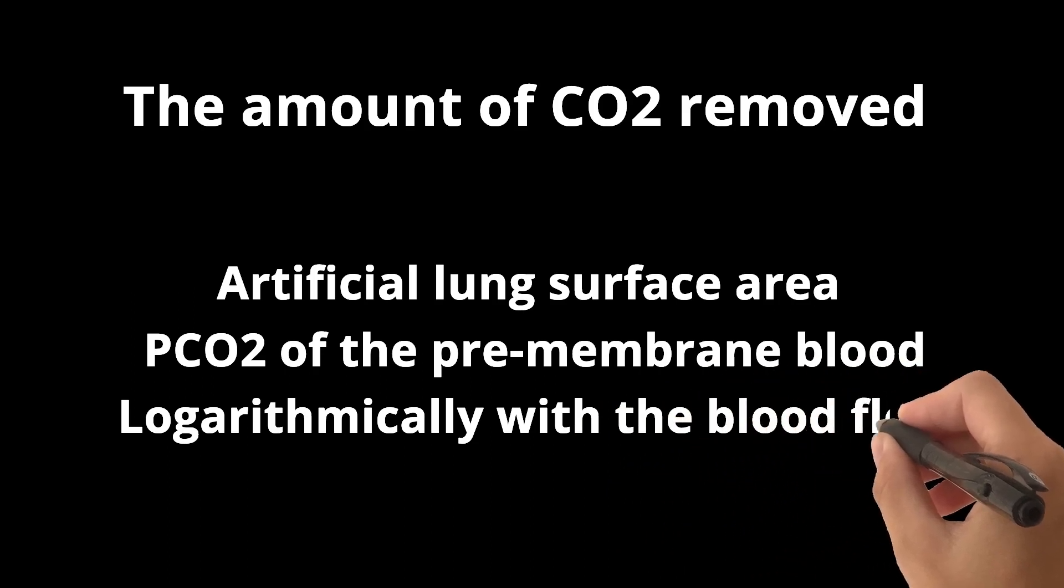The amount of CO2 removed for a given sweep gas flow increases linearly with the artificial lung surface area and the pCO2 of the pre-membrane blood, and logarithmically with the blood flow.